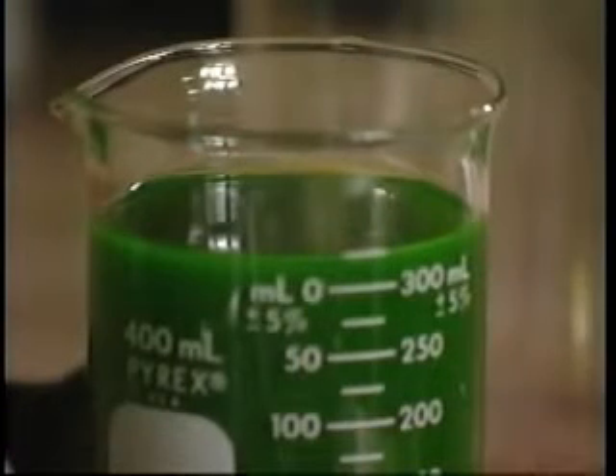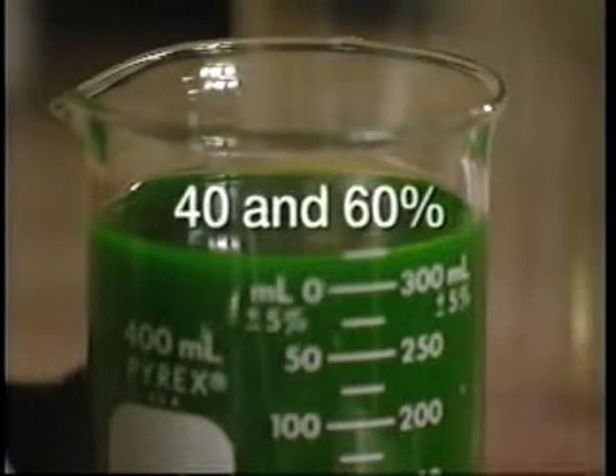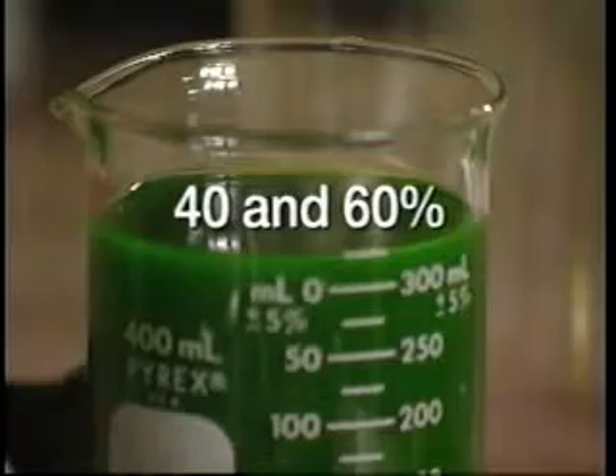Okay, assuming we have the proper water quality, the next important ingredient is antifreeze. Antifreeze not only protects the engine from freezing, it also raises the boiling point of the coolant. The most commonly used antifreezes are ethylene glycol mixtures. Recently, propylene glycol products have become more available. Regardless of which mixture is used, the important thing about antifreeze is the concentration. It should be between 40 and 60%, with a 50% level being optimum.